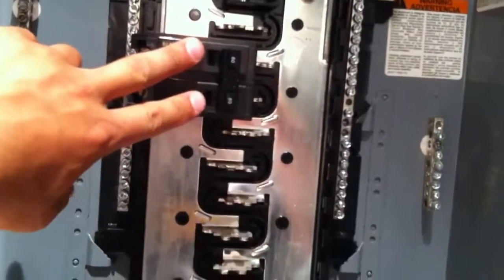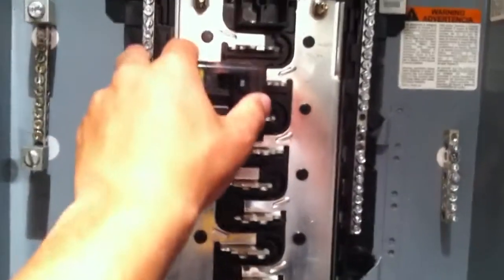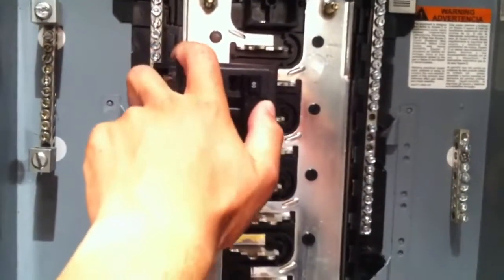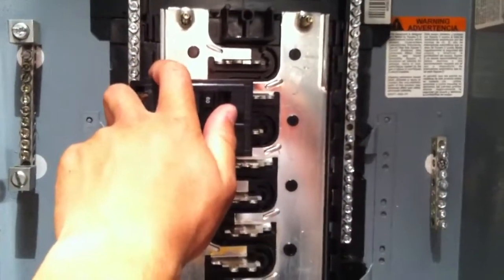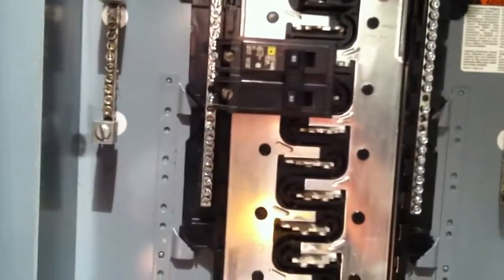So it looks like a normal circuit breaker, and it'll be labeled main, principal, main breaker, whatever, so you'll know it's the main circuit breaker. But it actually feeds in through the bus bar. That's the only breaker that works backwards.